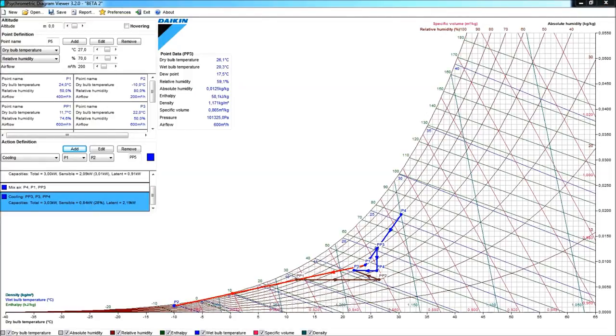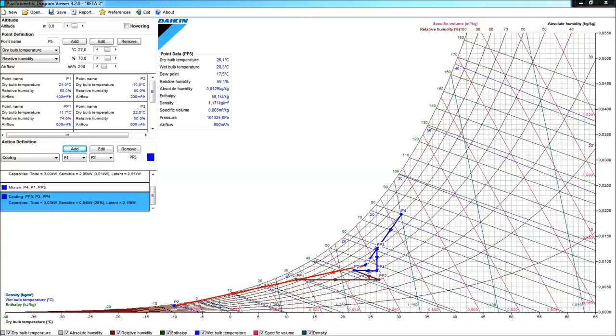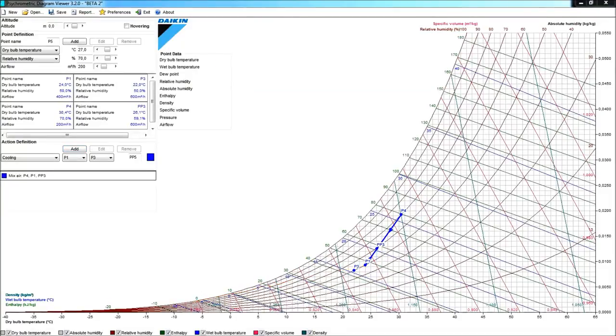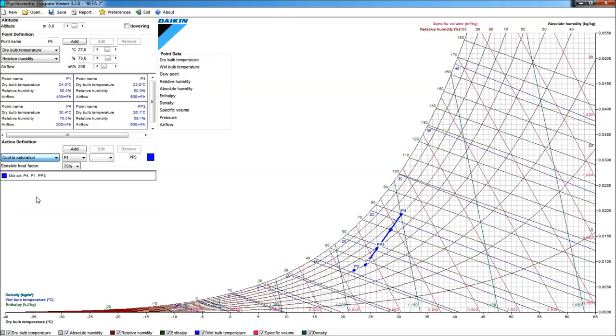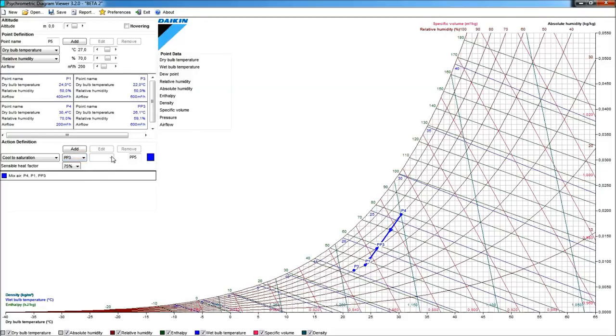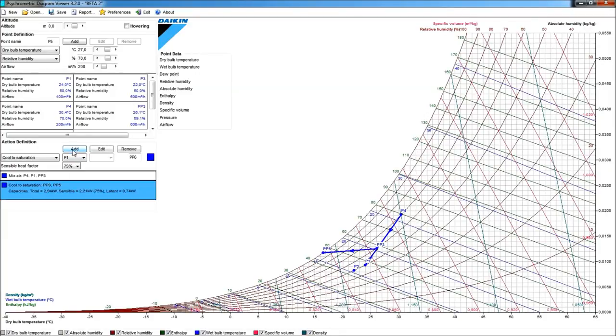But, to continue that exercise, let's throw away a couple of points that we no longer need, or that would only confuse us. Okay, so let's simplify that drawing slightly. So, we said it was not all that simple to go from PP3 to P3, and what is really happening is that we will need to cool that mixing point to a condition where we will reach the saturation line. So, this we will be able to cool with a sensible heat factor, let's say about 75%, and we will go from the point PP3 to find our cooling on the saturation line. That is what's happening when I add this point.